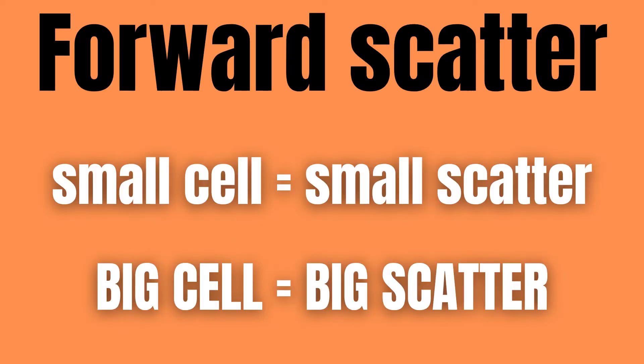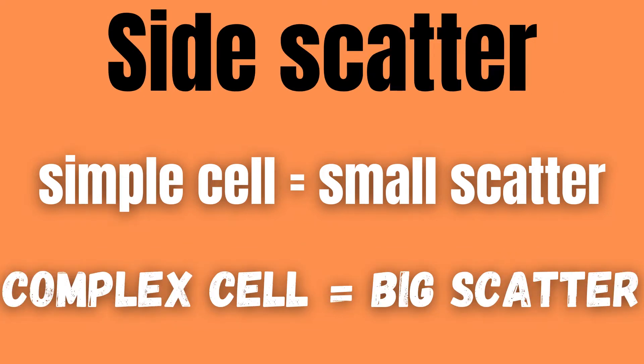Forward scatter is proportional to the size of the cell, while side scatter is proportional to the complexity of the cell. Both the forward and side scatter get detected and converted into an electrical pulse, which is directly proportional to the amount of scattered light.